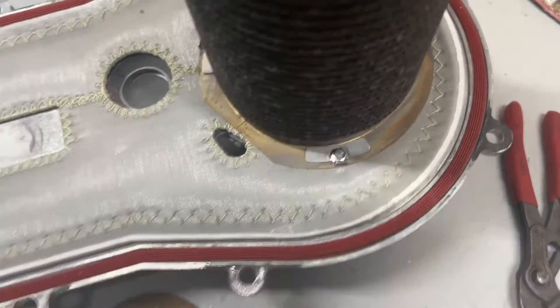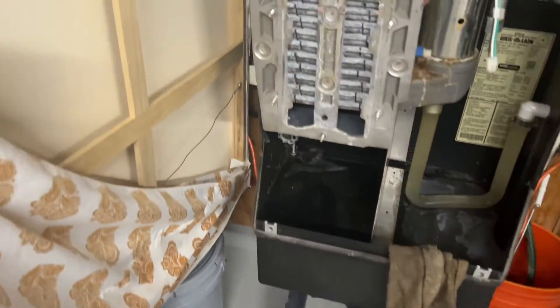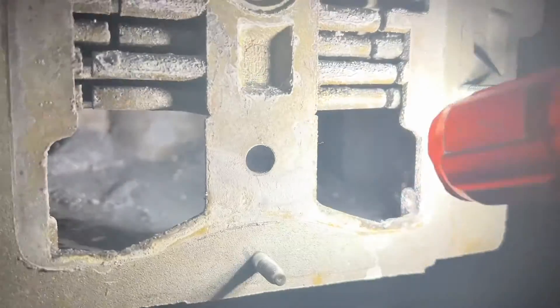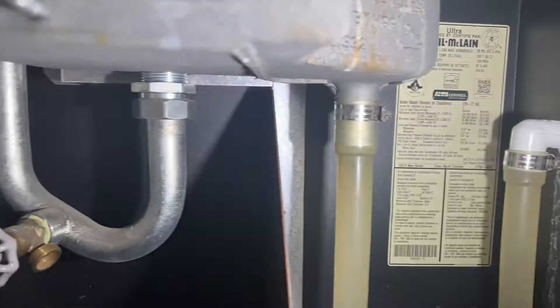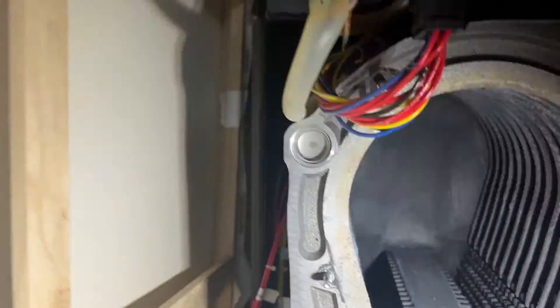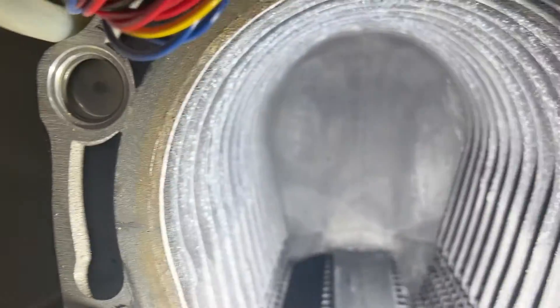So this is what that new gasket looks like, and that new refractory. They give you new bolts for the burner gasket and some others which I'm going to throw on. I'm just going to show you the difference in the heat exchanger shape. I was checking at the bottom corner, making sure there wasn't any breaking apart or holes forming — which there's not. The inside looks much better too, but I gotta finish up with the front plate.